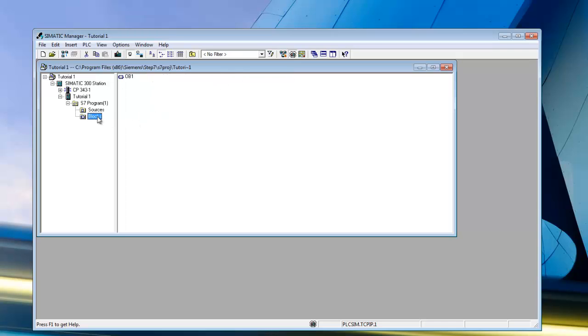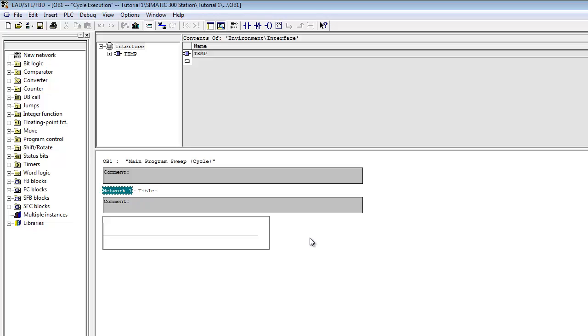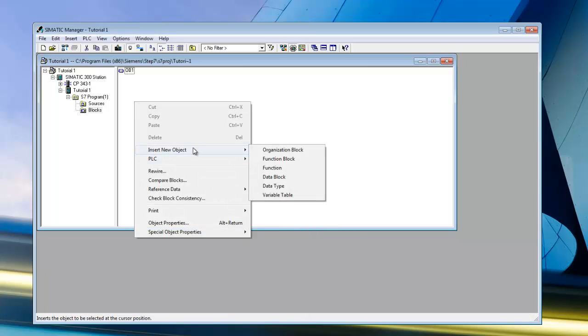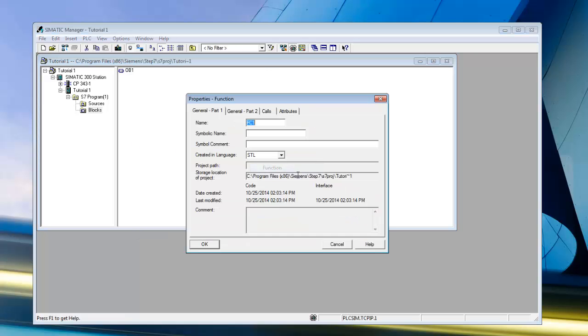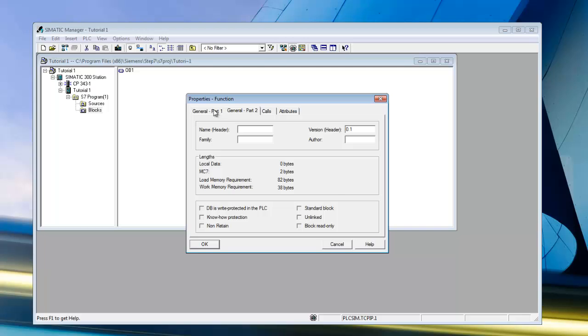We can come down here and get started. We have our Organizational Block — as I said, this is the first block that gets scanned and executed. We could do our ladder in here and it would work fine, but we're going to use this only as an organizational block, so we'll close it. Instead, we'll right-click, insert a new object, and put in a function block. We'll call it Line One, create it in Ladder language, and add a comment saying 'Packing Line One'. Select OK.